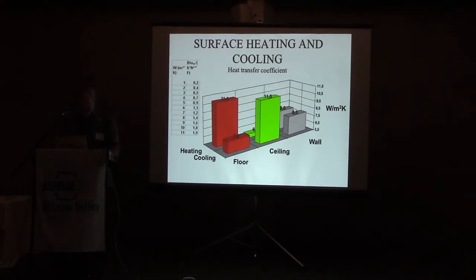So one thing is the capacity of radiant heating and cooling systems. And that relates to the heat transfer coefficient you have. And here we have a difference between the different systems where you have the pipes embedded. The way you calculate the heat transfer in the structure follows the same rules. But the difference is at the heat exchange at the surface. So if we take a floor and we warm it up so it's warmer than the room, we can go up to a heat exchange coefficient of about 11. Half of this, 5.5 watts per square meter per degree, is radiation. And the radiant part of the heat exchange coefficient is the same.